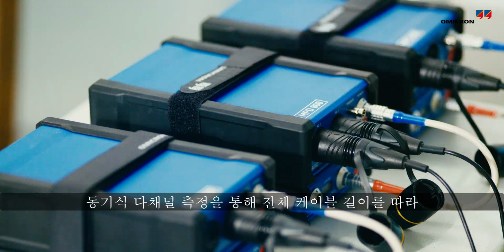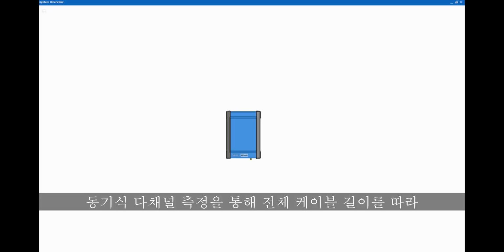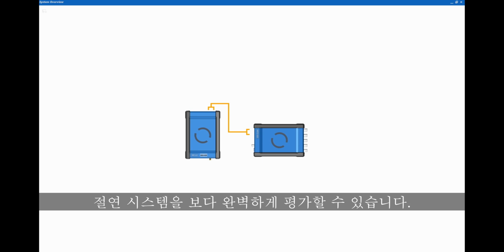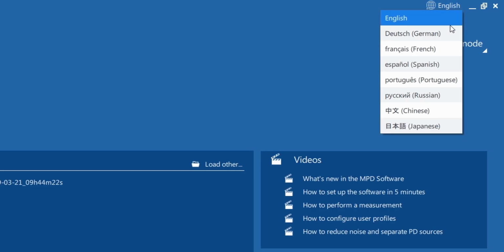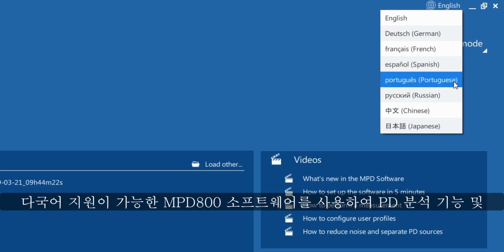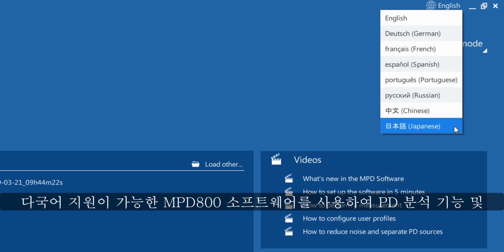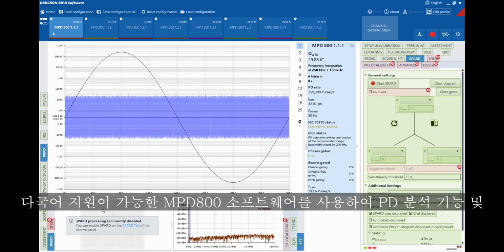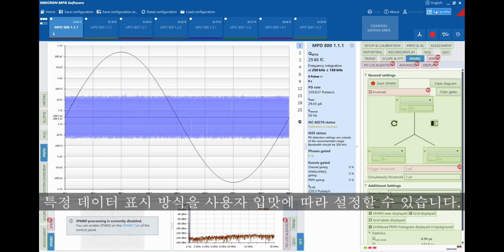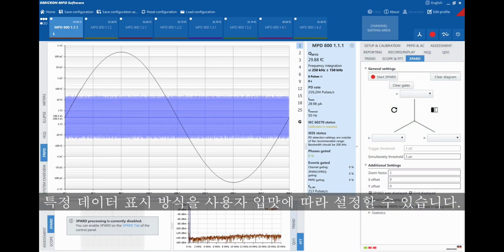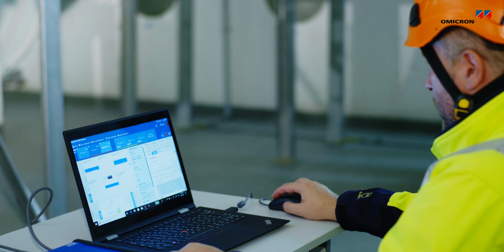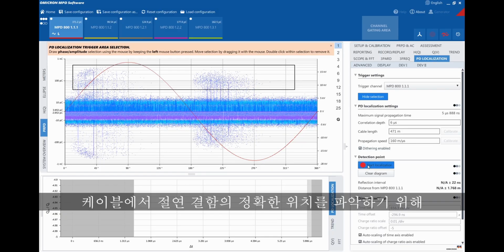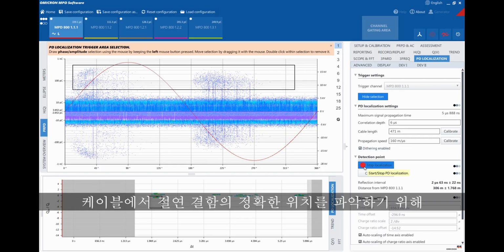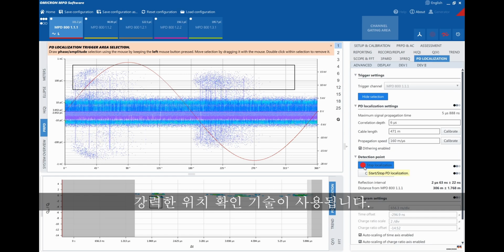Synchronous multi-channel measurements ensure a more complete assessment of the insulation system along the entire cable length. The system's multi-language software allows you to select only the PD analysis tools you need and how data is displayed for specific tests. Powerful localization techniques are used to pinpoint the exact position of insulation defects in cables.